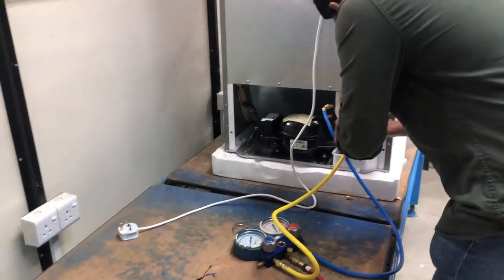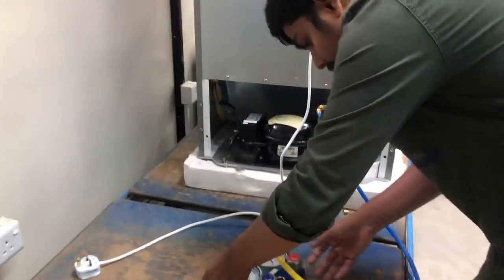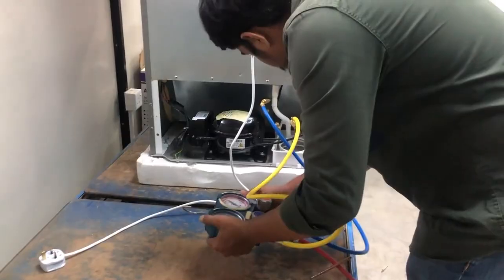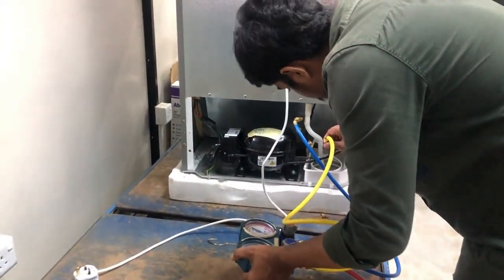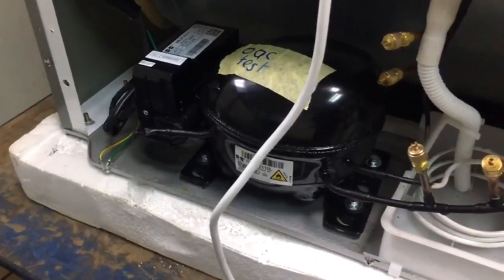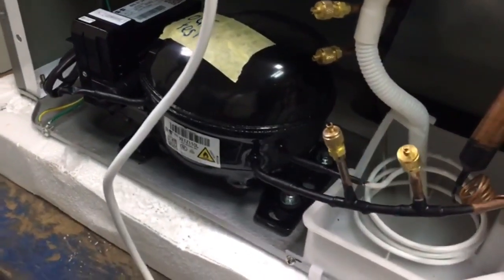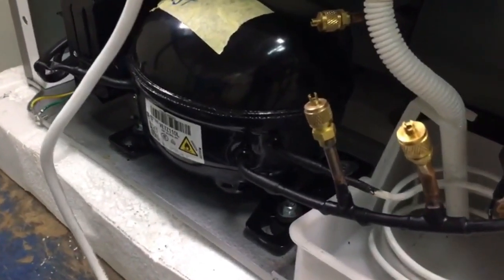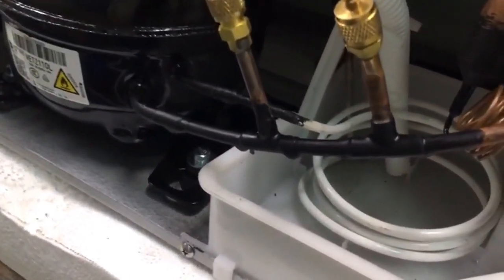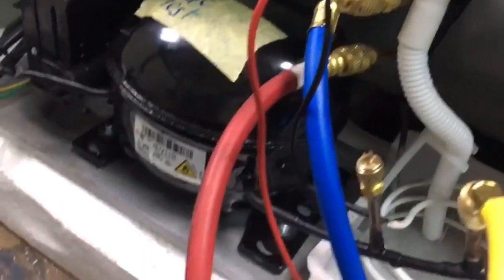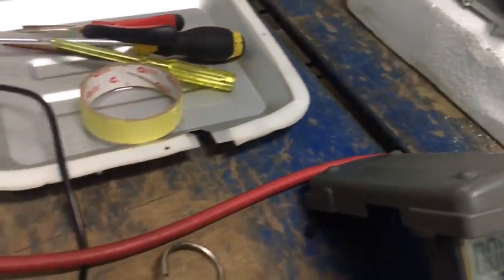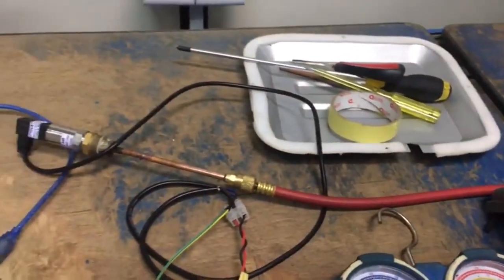For the analog pressure meters, we directly connected them to the compressor's inlet and outlet. To enable this, we modified the compressor by cutting its inlet and outlet points and installing T-bars. Four T-bars were used to connect both the pressure transducers and analog pressure meters at these points, allowing us to measure the pressure at both the inlet and outlet accurately.